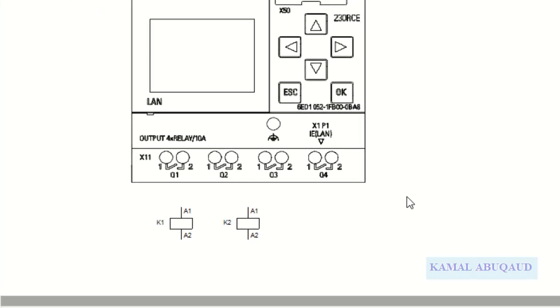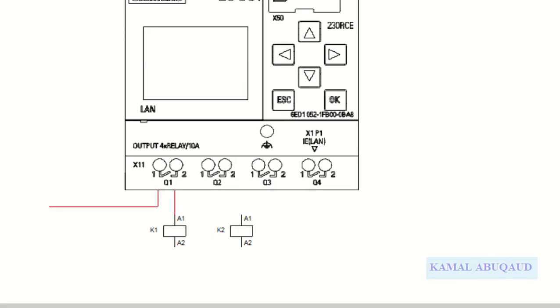To connect the relay coil to the PLC output, we connect one side of the relay coil to the PLC output terminal. The other terminal of the PLC should be connected either to live if the relay coil is an AC coil, or to the positive supply terminal if it is a DC coil. I'm assuming a DC coil, so one side is connected to the positive terminal and the other side is connected to the negative terminal.